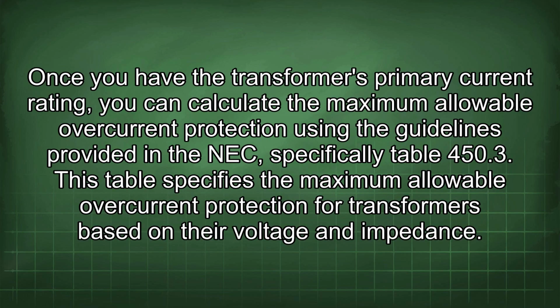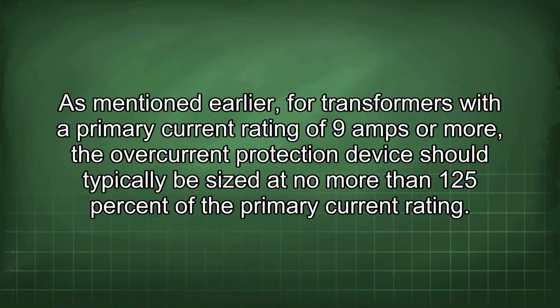Once you have the transformer's primary current rating, you can calculate the maximum allowable overcurrent protection using the guidelines provided in the NEC, specifically Table 450.3. This table specifies the maximum allowable overcurrent protection for transformers based on their voltage and impedance. As mentioned earlier, for transformers with a primary current rating of 9 amps or more, the overcurrent protection device should typically be sized at no more than 125% of the primary current rating.